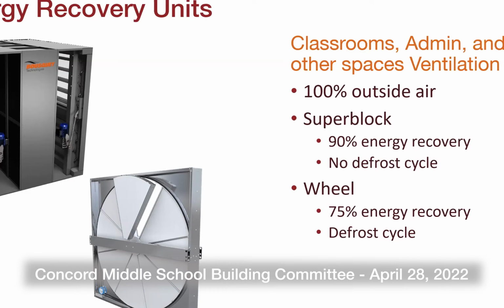We're looking at a couple of different technologies to do the energy recovery. One is Superblock, shown in the top left, which can get 90% energy recovery. Another is energy recovery wheels, more the tried and true path—these have about 75% energy recovery, but they do have a defrost cycle, which unfortunately takes away some of their energy efficiency in the winter.